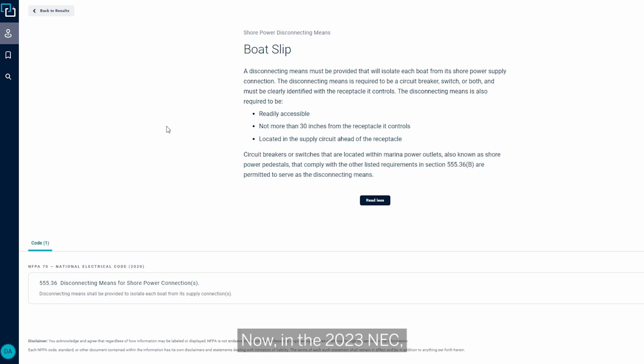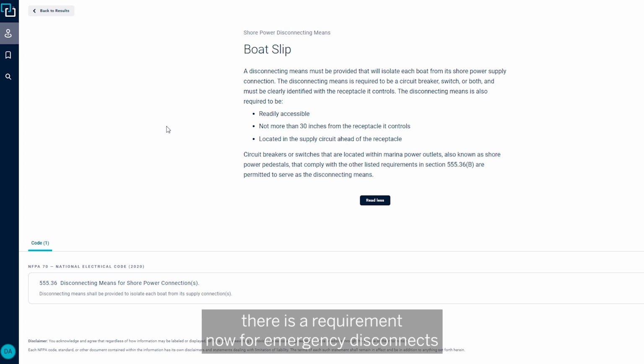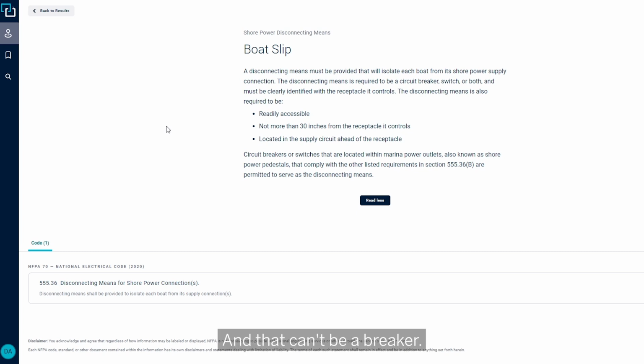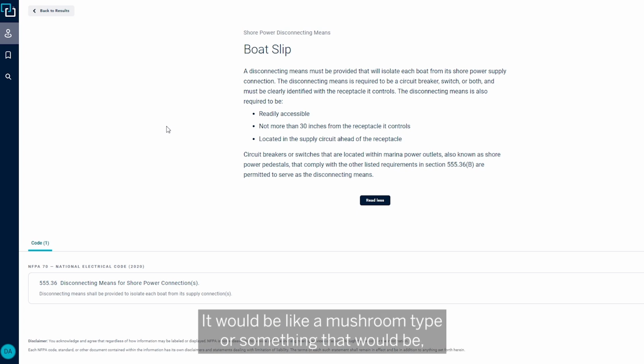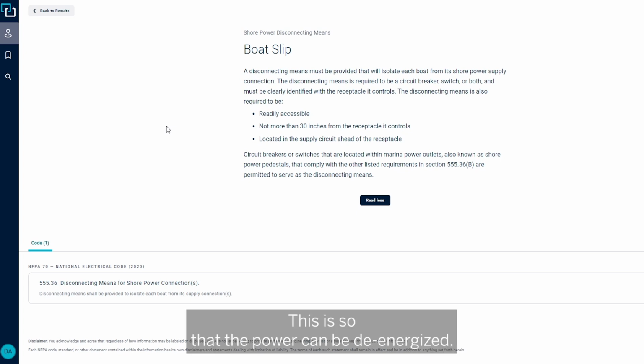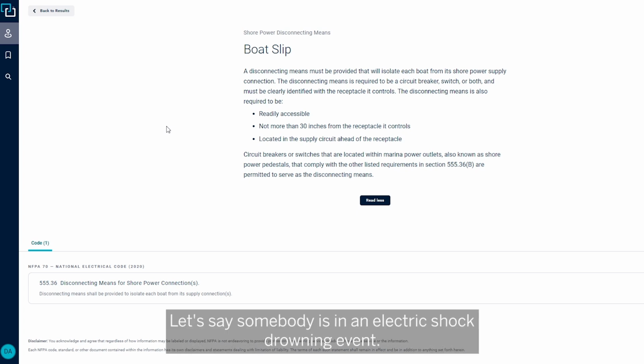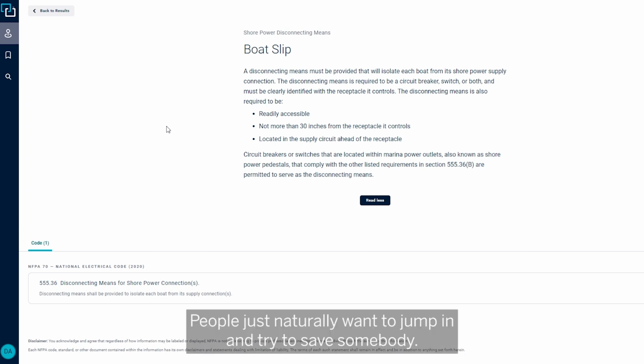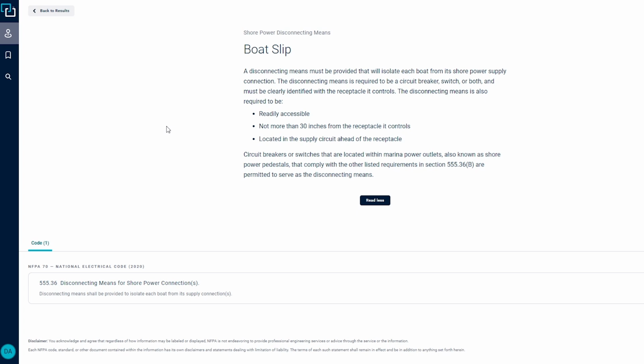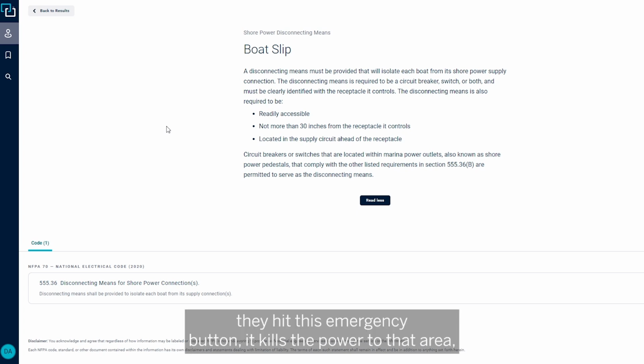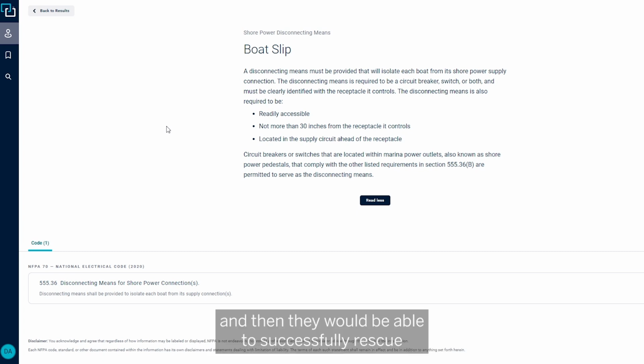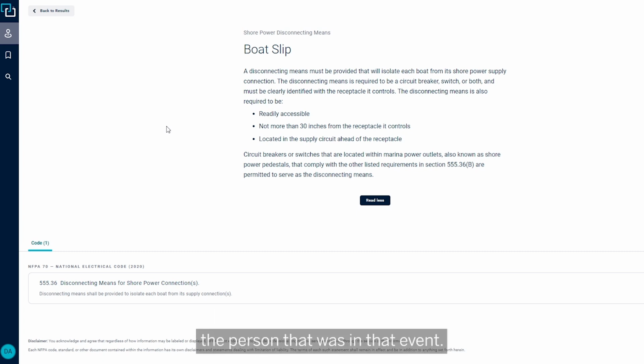Now in the 2023 NEC, there is a requirement for emergency disconnects that will remove power to circuits supplied by marina power outlets. And that can't be a breaker. It has to be an emergency disconnect, like a mushroom type or something that would be easily gotten to. This is so that the power can be de-energized. Let's say somebody's in an electric shock drowning event. People just naturally want to jump in and try to save somebody, and they need to be aware that they could be subjected to that ESD as well. So they hit this emergency button, which kills the power to that area, and then they would be able to successfully rescue the person that was in that event.